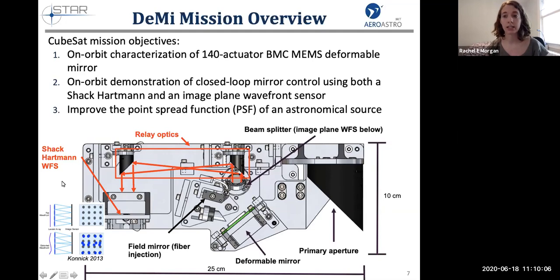The lenslet array takes the incident wavefront and splits it up and focuses it into a grid pattern of spots on the camera. When the light is distorted, these spots actually move, and you can measure the displacement of these spots to back out the shape of the distortion and use that information to control the deformable mirror to correct them and steer the spots back to their nominal position.